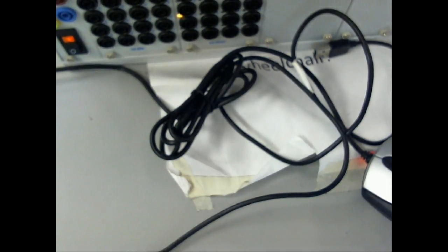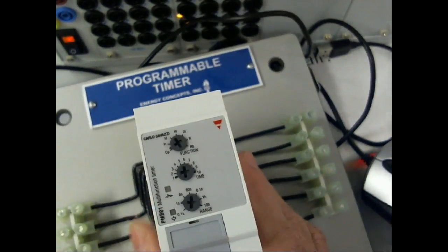Yeah, so what I passed around was an off delay timer, but the off delay timer would always be an off delay timer, right? So if I had a bunch of off delay timers and on delay timers, and I kept spare parts, I'd have to keep all these spare parts. If I had a timer that I could program to be a what? Off delay, on delay, retentive, whatever timer I need, then all I would do is keep one spare part. So this is a programmable timer.